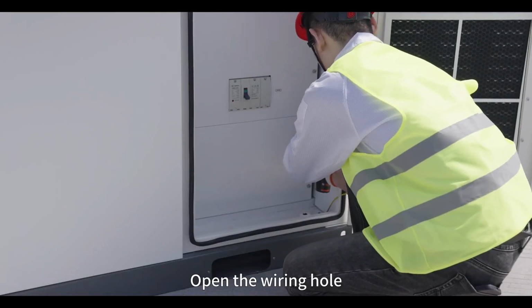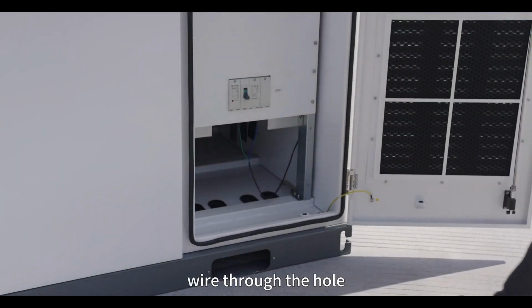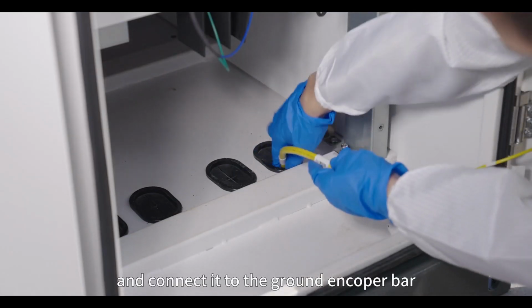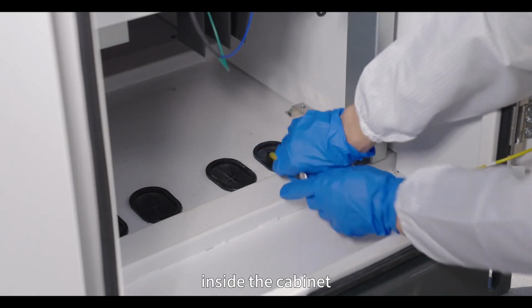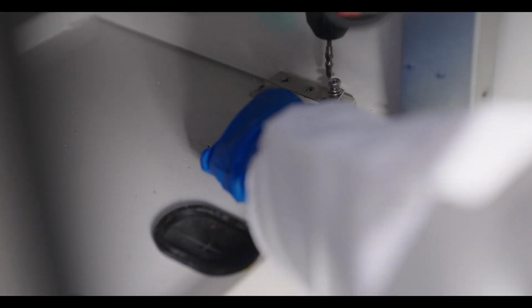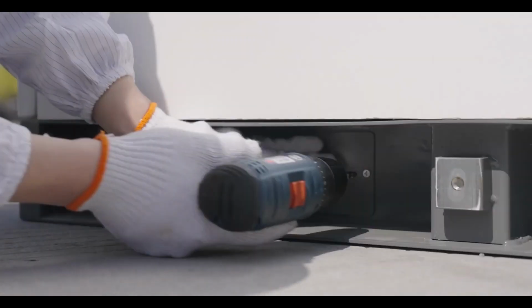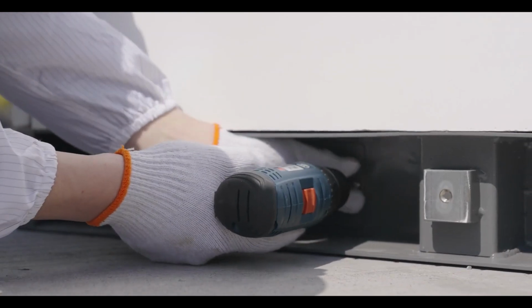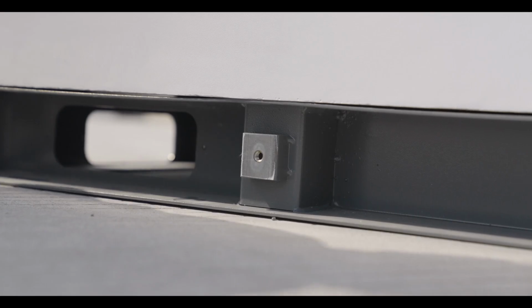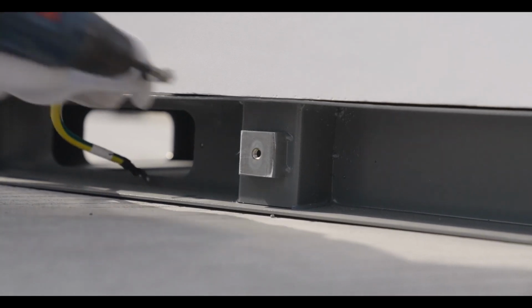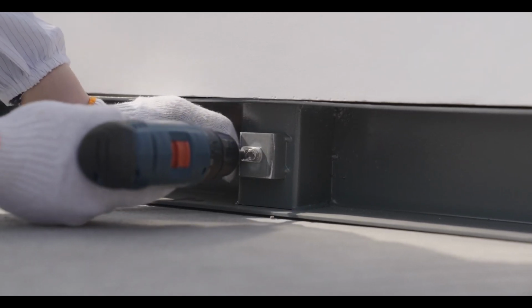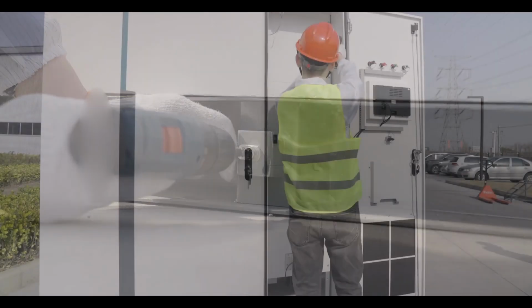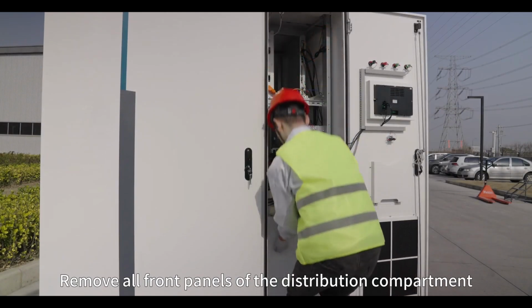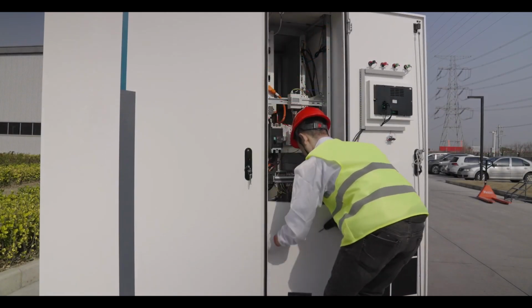Open the wiring hole. Pass the protective ground wire through the hole and connect it to the grounding copper bar inside the cabinet. Remove all front panels of the distribution compartment.